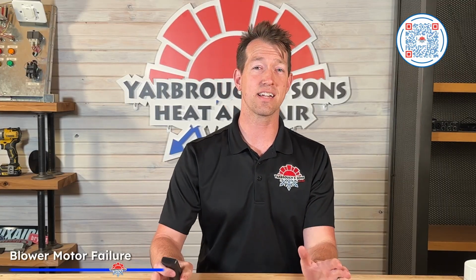Okay, so the diagnostic sign to watch out for. All right, guys, watch out for this. Does air come out of your vents at all? And is the pressure what you're used to? Okay, weak airflow with a running system is often a blower motor issue before it's anything more serious.